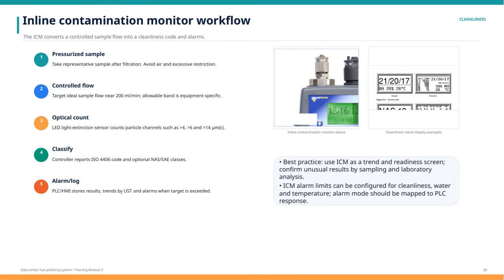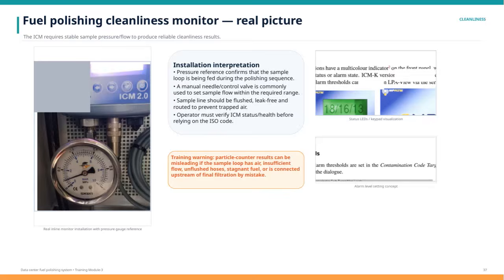Alarm settings for cleanliness, water content, and temperature can be customized, and alarm responses should be integrated with the PLC for effective management. This approach ensures continuous and proactive fluid cleanliness monitoring within the fuel polishing system. Here, we have a real picture of the Fuel Polishing Cleanliness Monitor, or ICM for short. One crucial point to understand is that the ICM needs a stable sample pressure and flow to provide accurate cleanliness results. Without this stability, the readings could be unreliable.